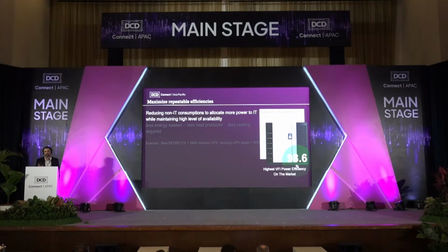I want to use the example of a new UPS product we're launching, where we move efficiency from 97.5 to 98.6 percent. That one point of efficiency is actually a 45% decrease in inefficiencies, which is directly usable by the IT equipment.